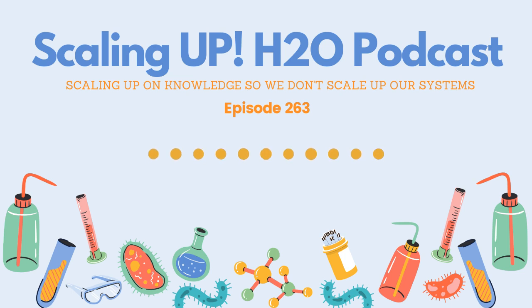What that means is flow is stopped within that little dead leg of nipple or pipe, so we're not getting the cleaning effect of the water moving through the piping. As water flows, it takes all the biomaterial growing in the pipe with it so it can be flushed out. If we don't give the water a place to flow to and biocide to freely reach, it can grow uncontrolled. As it grows, it can start sloughing off and getting into the mainstream of water, creating problems downstream. That's why dead legs are such an issue, and why you want to identify all of them in your water management program.